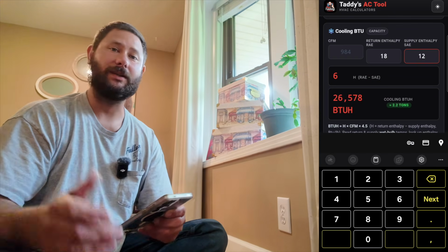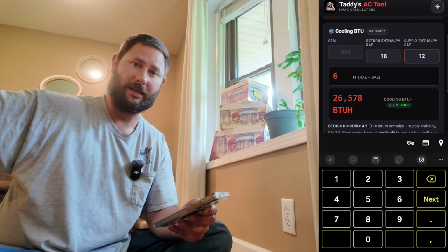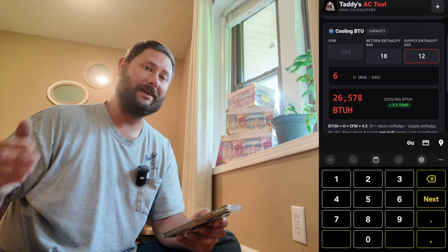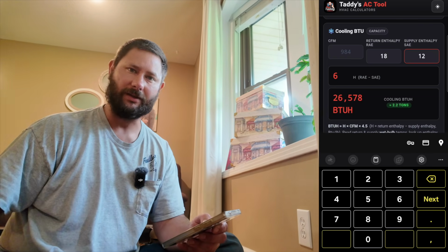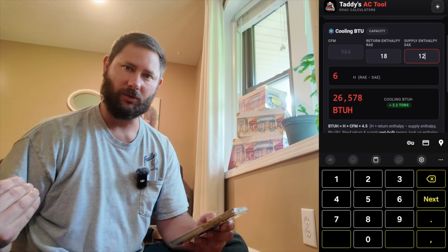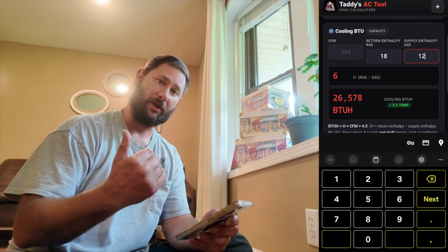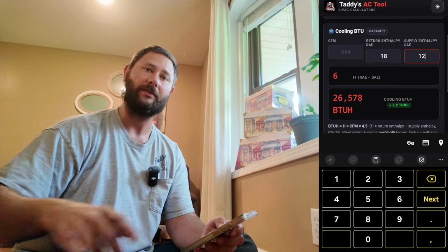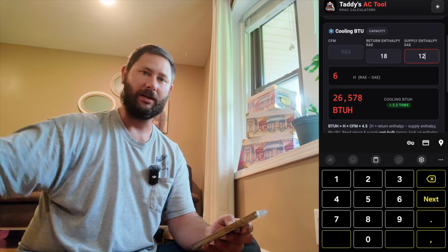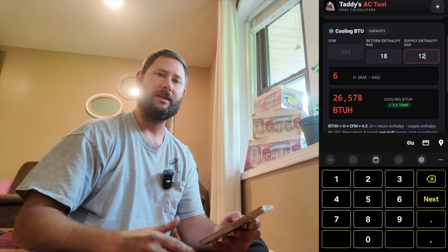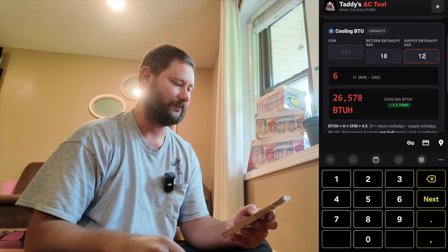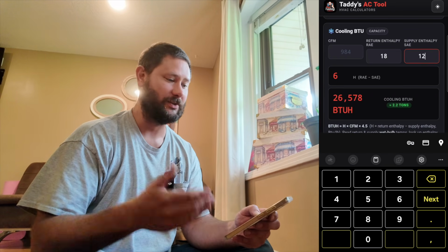It could be the ductwork. It could be that we're actually not going into second stage. But this is a great tool because I can just screenshot this real quick, or I can go over to the customer, whether it's heating, whether it's cooling, and I can go, hey, there's a problem and it's with your duct, and we found this, and I got the pictures, and we need to modify the duct, or we need to install new ductwork, or it's leaking. We need to air seal it. So it's great. This is a great tool.